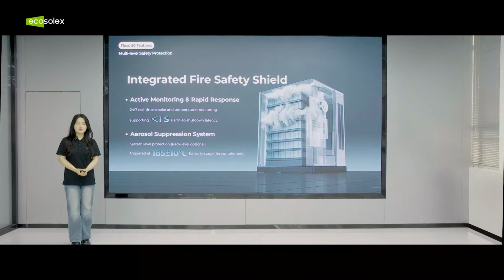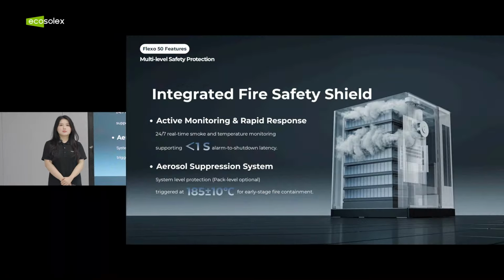We also have the ultimate shield, the integrated fire safety shield. With 24/7 active monitoring, our system triggers a sub-second shutdown when smoke or temperature anomalies are detected, ensuring instant danger isolation. The aerosol suppression system then deploys. As a system-level safeguard with optional pack-level modules, it triggers at about 185 degrees to suppress fire early and contain damage.